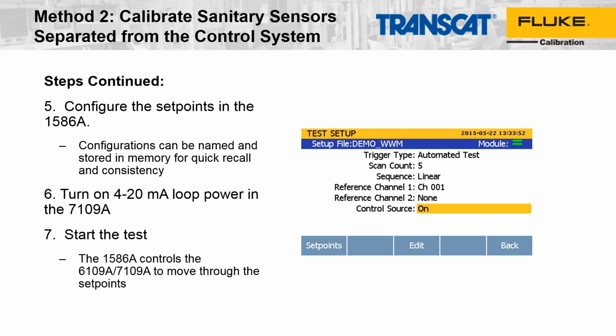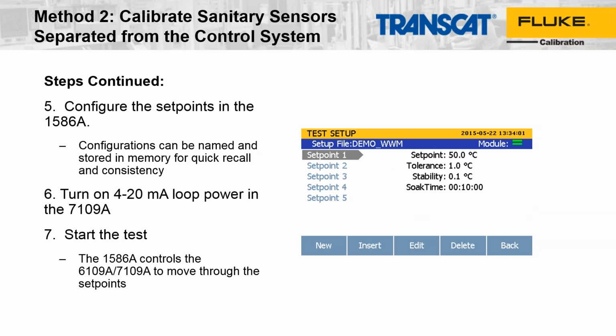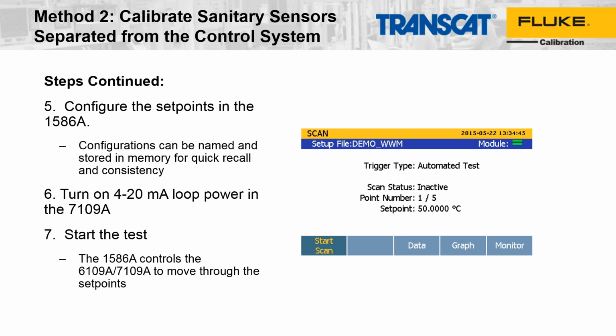We're going to use control source. That way the 1586A will tell the 7109A to transition to the temperatures as needed, so you don't have to use any external software to do this. And this is where you are setting up the set points, the tolerance and stability, and soak times or dwell times for each set point. And then you go ahead and hit start scan when you're ready to start running it.